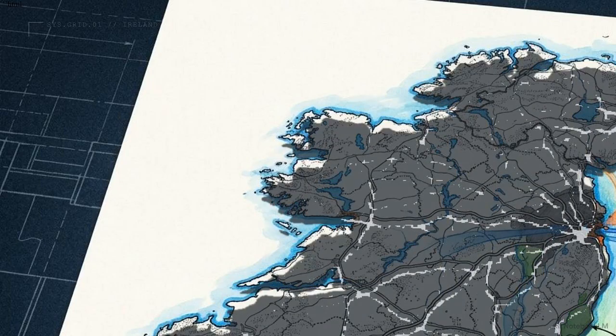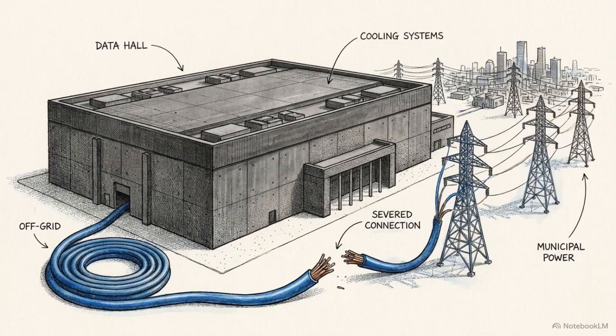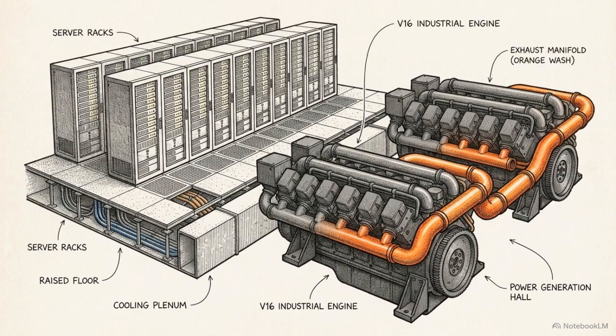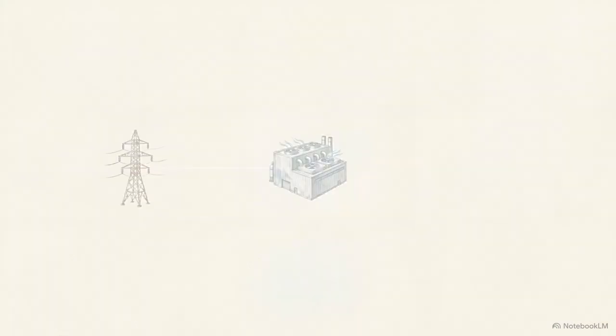National grids rely on aging infrastructure that lacks the capacity to route these massive volumes of electricity into concentrated geographical hubs. In saturated markets like Ireland, network operators have responded by denying grid access or imposing connection delays that can exceed a decade to protect the stability of the public system. To deploy on schedule, high-density facilities must decouple their development from public grid dependence. Modern data center design integrates multi-megawatt on-site generation as a mandatory primary component rather than an occasional backup system.